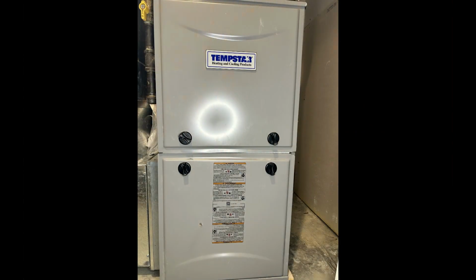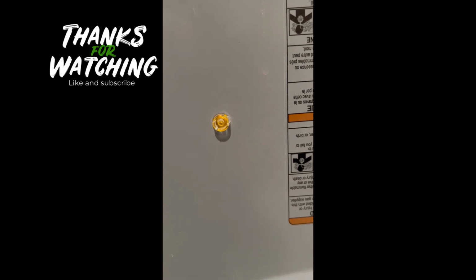To get to the error code booklet, you will need to remove the bottom door. This in turn will release the door safety switch, killing the power to the furnace. You will lose the code. Some furnace models will show you how to recall error code history, but that is a whole process you can avoid, and not all offer this.